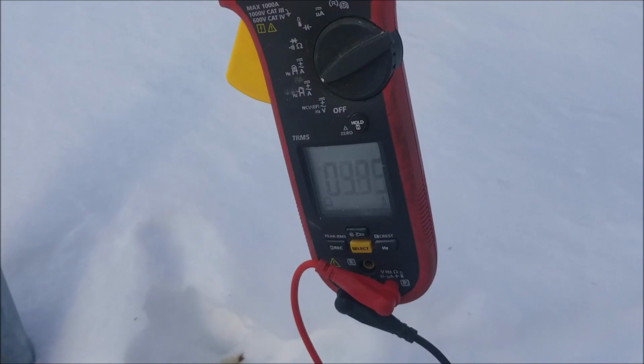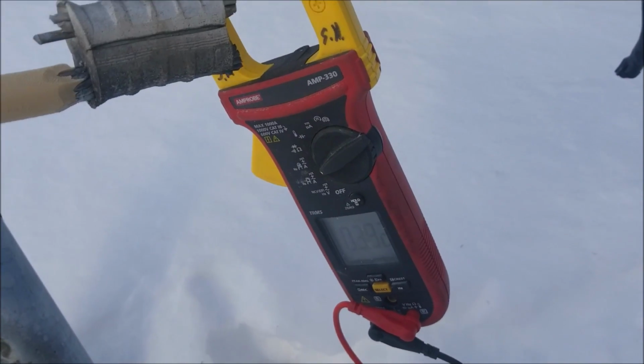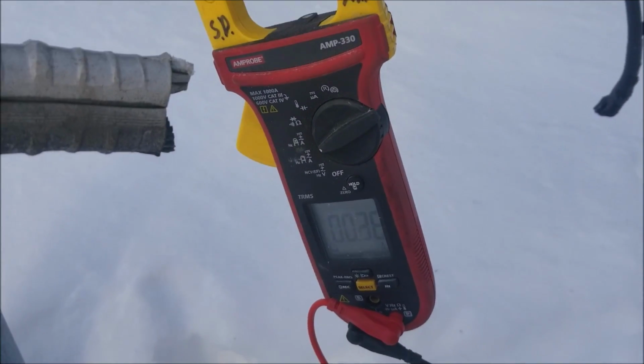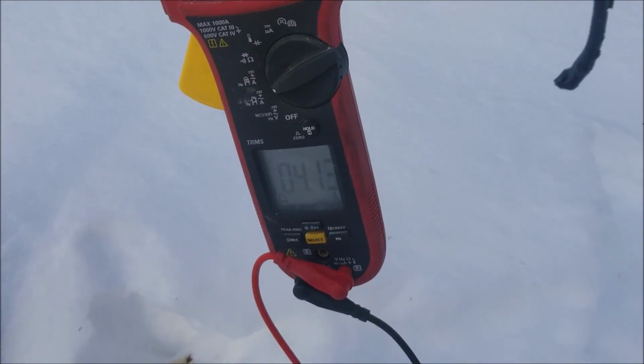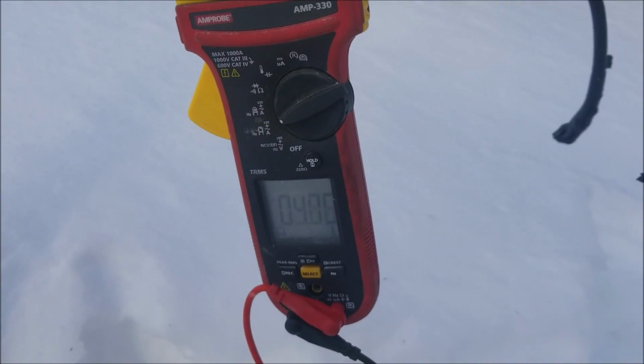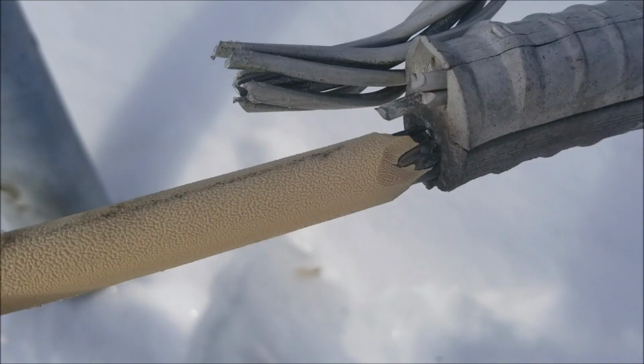It was later discovered that the unbalance from the remaining services on that particular transformer were using this particular path to ground, as someone had stolen all the copper wire intended to bond through our circuit through the underground dip and back to source.